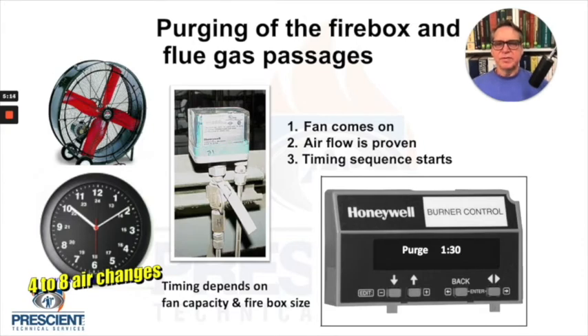So after the limit string is made and all of those devices are indicating that you're in a ready to start position, then purging of the firebox and flue gas passages starts. So a fan starts, but it's not enough to know that the fan started. The burner management system needs to know that you have the right airflow. So there's generally some type of means to prove airflow and means to prove that the fan has started. There's generally two conditions that need to be met.